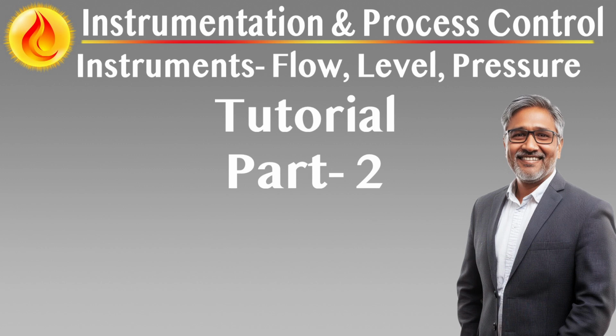Inline instrumentation must meet or exceed the pressure temperature limits of the piping class or equipment to which they are attached. This includes sensor housings, flanges, bolting, and wetted parts. Certification and mechanical ratings must be traceable and verifiable. For equipment with no piping class, e.g. vessels, design pressure and temperature ratings must still govern selection.